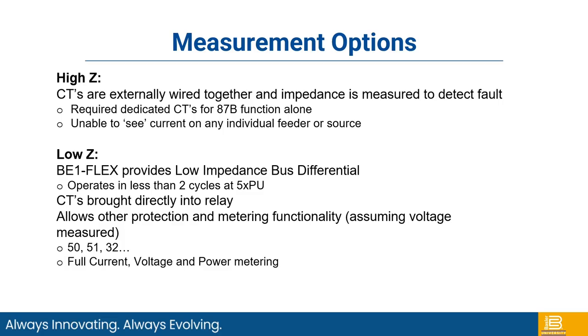The BE1-FLEX provides low impedance bus differential, as I mentioned, and operates typically in less than 2 cycles at 5 times pickup. The CTs are brought in directly into the relay. So for instance, if you have 5 breakers, a main and 4 feeders, you would wire the CTs in on all 5 of those breakers. This also allows for other protection and metering functionality, assuming you have a PT input, depending on the hardware limits. So you can also have all the other protection because differential will be enabled and you'll have full current, voltage, and power metering as well.